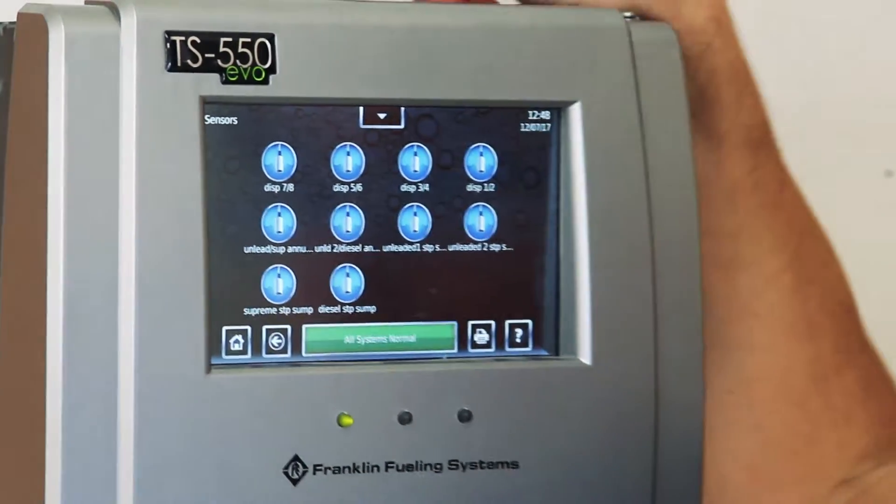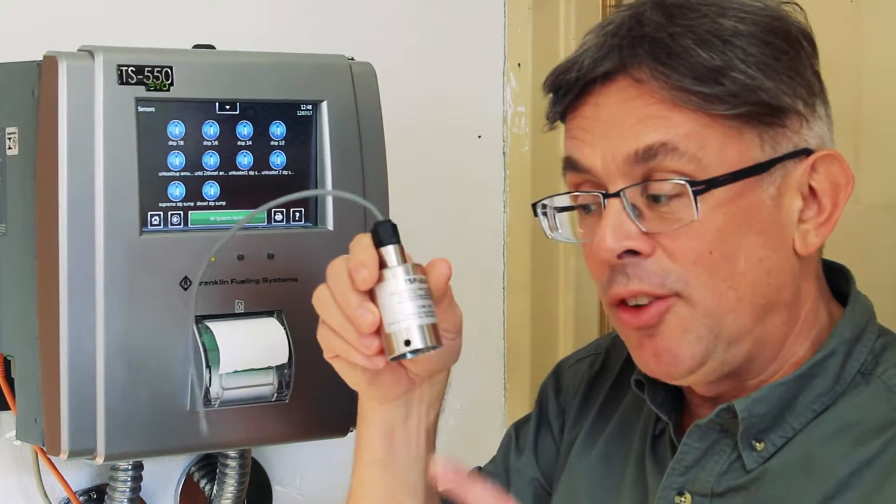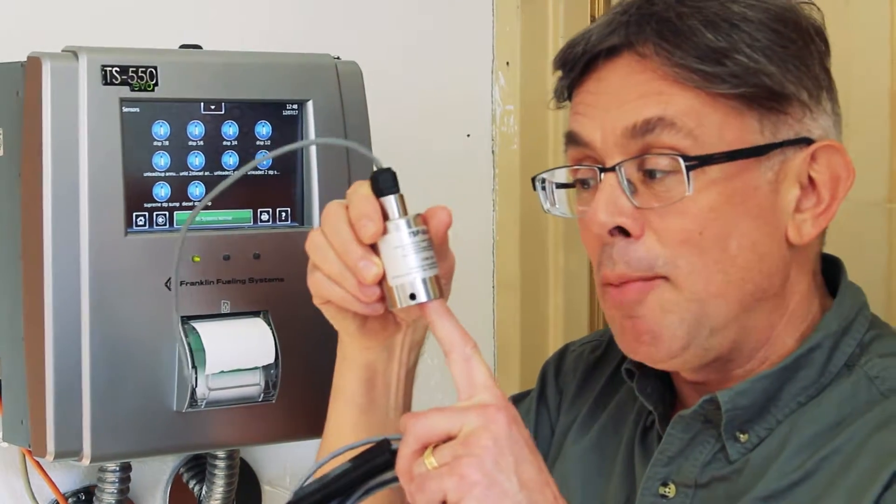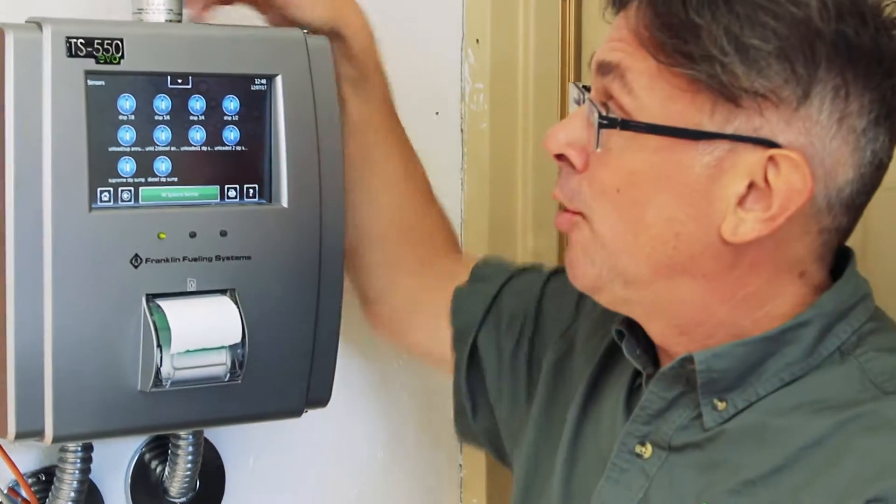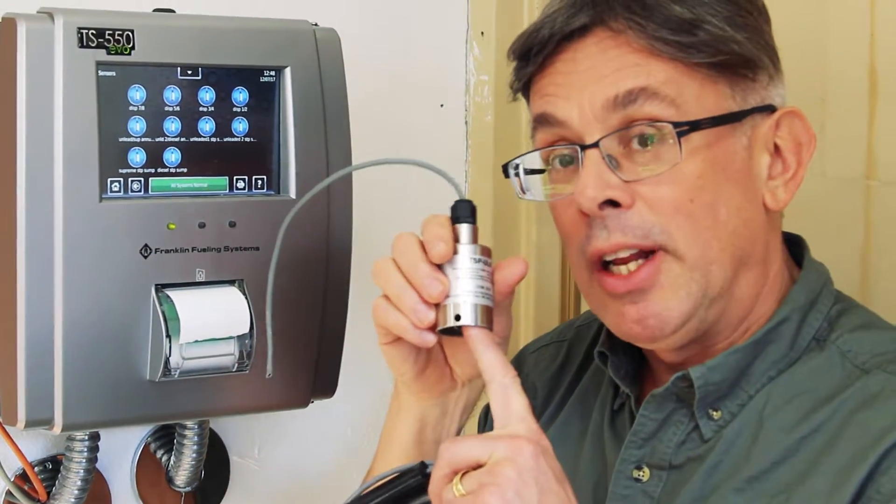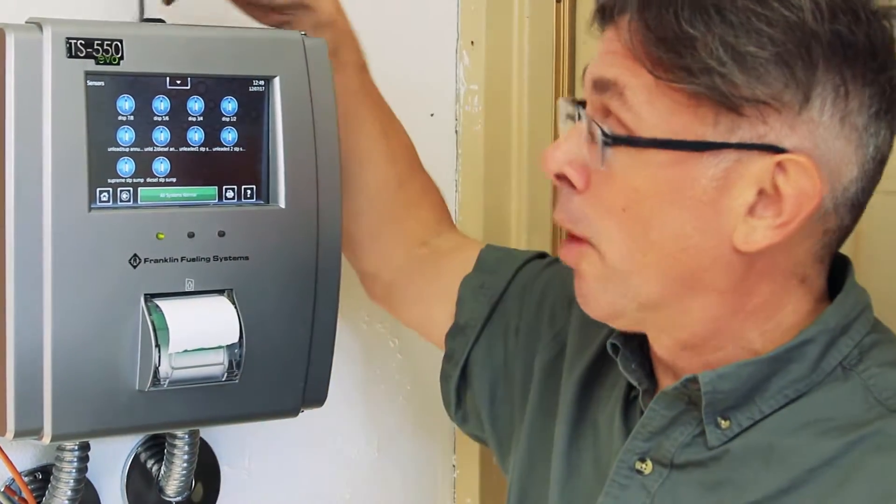There's a couple of different types of sensors out there. Some sensors are float sensors. They're activated by the rising of liquid inside a containment area, pushing up the float, sending a trigger to the alarm. This is what's called a non-discriminating sensor. This will tell you whether or not there's liquid in there, but it won't tell you if it's fuel or water.